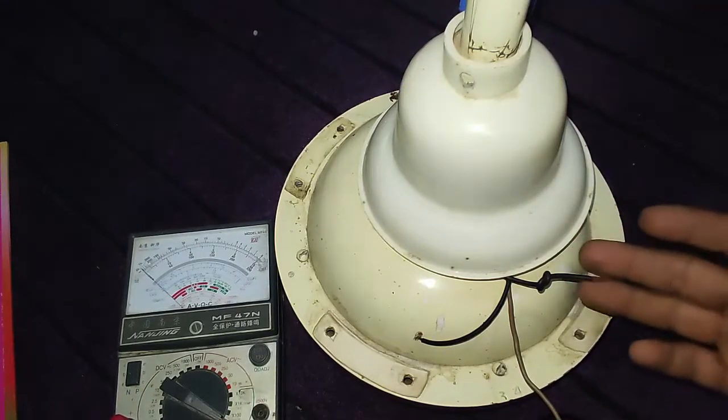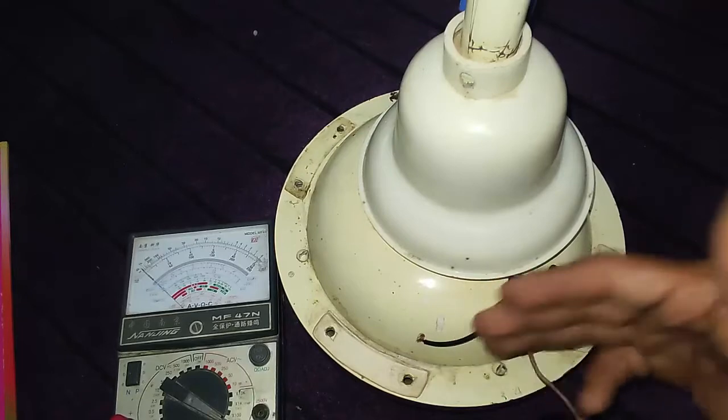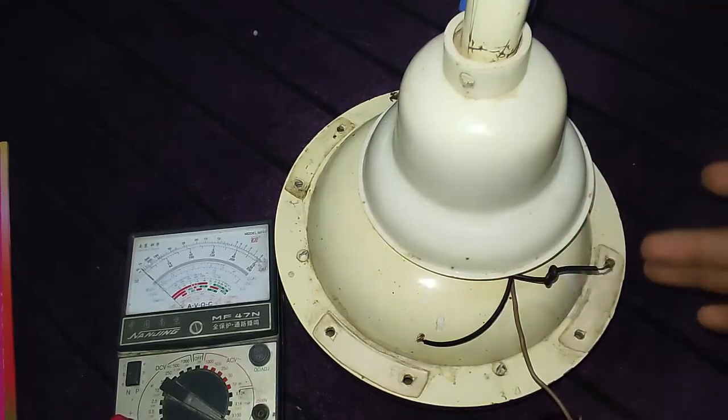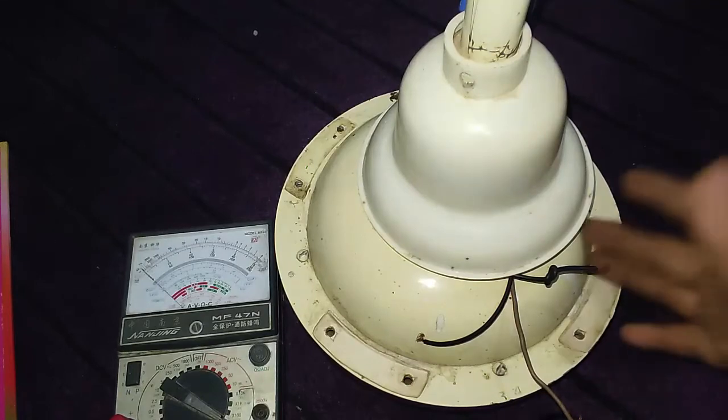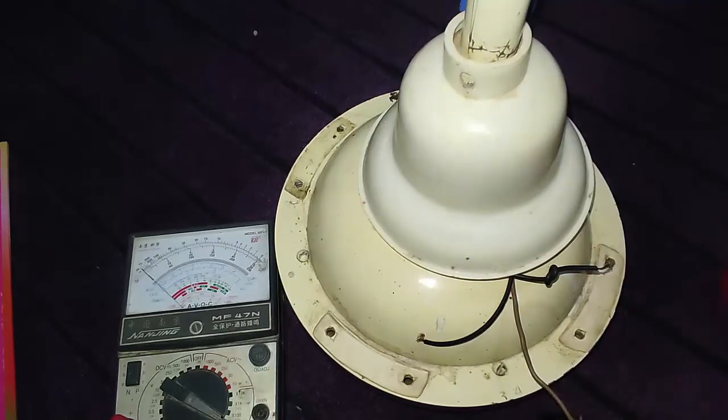As I already told you in my last video, the two wires which have high resistance will be start and run. First of all, I need to find out the common wire. This will be simple: if I find out that two wires have high resistance with one another, the third will be common.